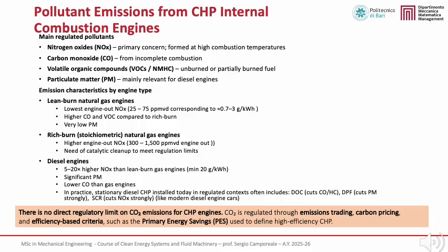Diesel engines present the most critical emission profile. They typically produce NOx levels 5 to 20 times higher than lean burn gas engines, often exceeding 20 grams per kilowatt hour, together with significant particulate emissions. On the other hand, diesel engines usually exhibit lower carbon monoxide emissions than gas engines. In practice, modern stationary diesel CHP units installed in regulated contexts are equipped with oxidation catalysts, diesel particulate filters, and selective catalytic reduction systems, similarly to modern diesel vehicles.